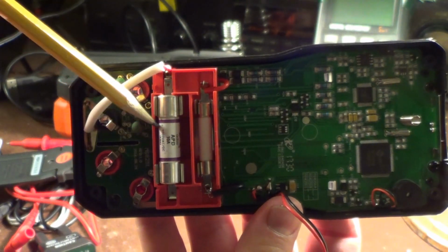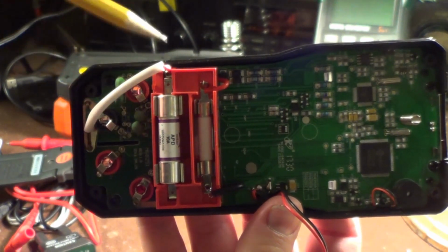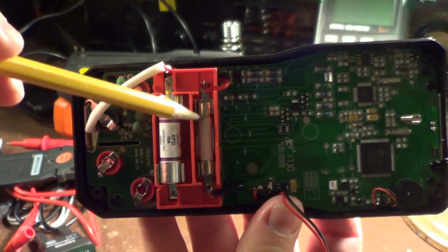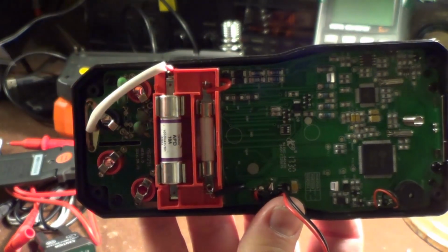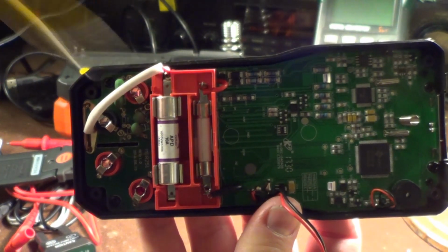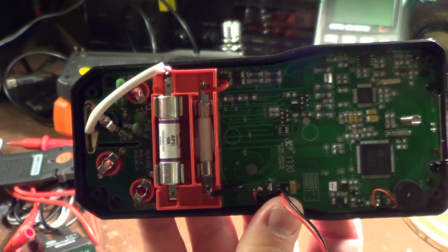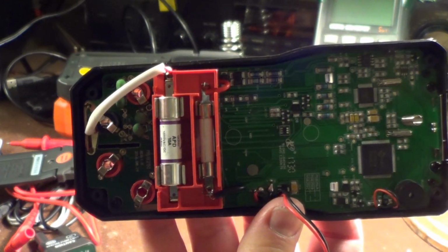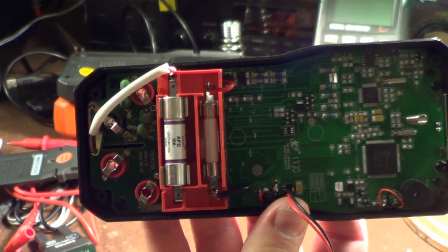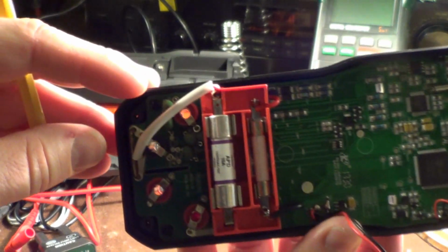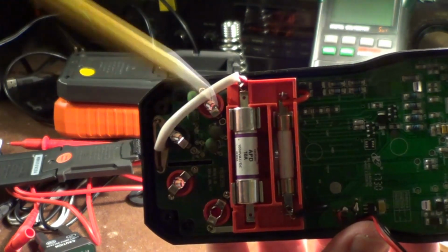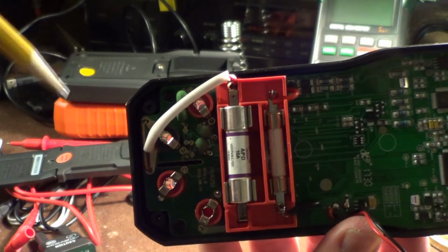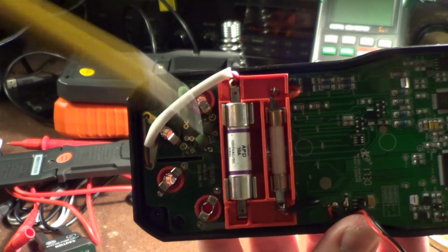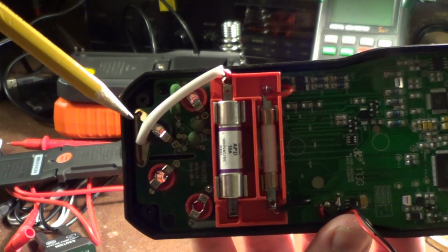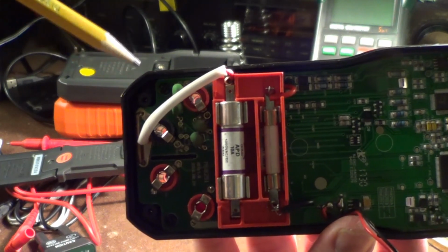It is actually rated for 1000 volts AC or DC. This smaller ceramic fuse, which is probably also HRC rated, also claims on its end caps to be suitable for use at up to 1000 volts. So, in theory at least it's possible, but again I'm not sure it's really a good idea, and here's why. Again, I'm not an expert on this. There are lots of people out there who know more than I do, but it just doesn't look like there's a whole lot of protection on this board.